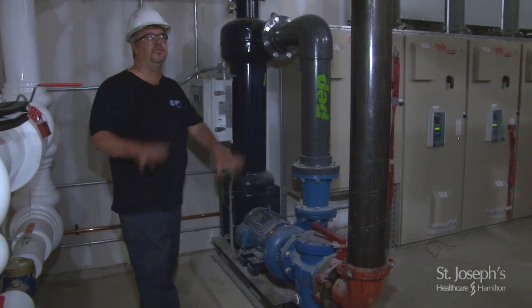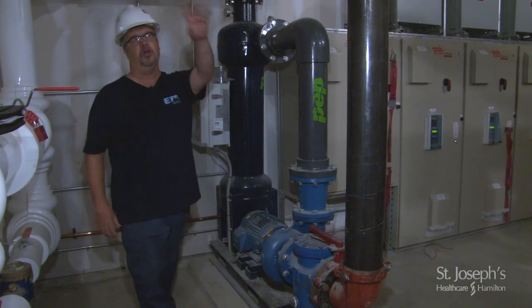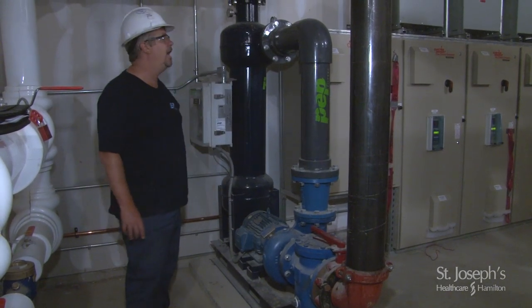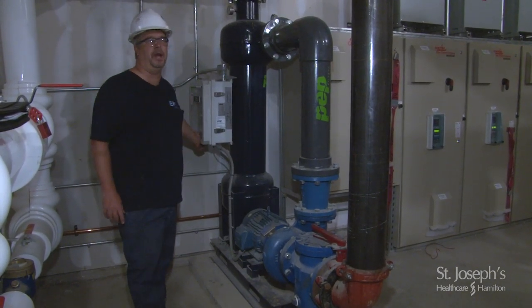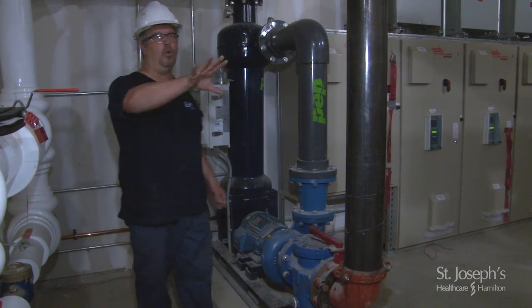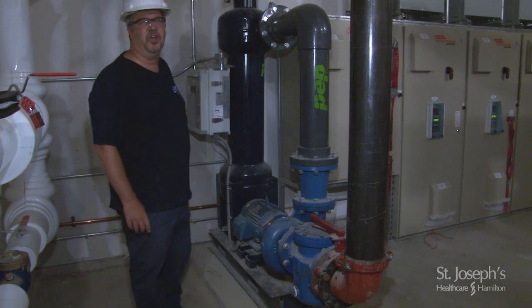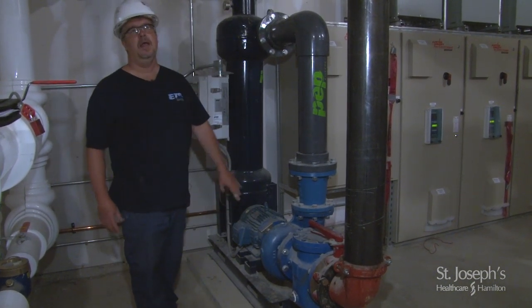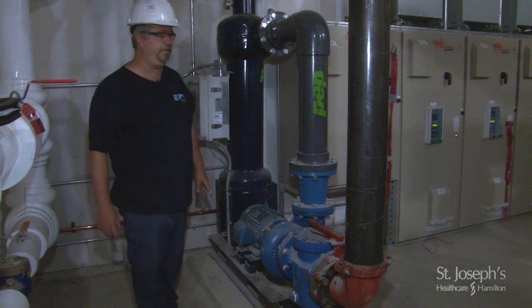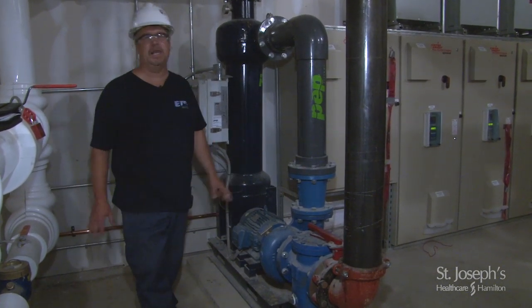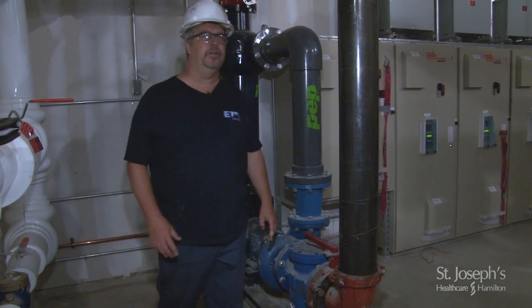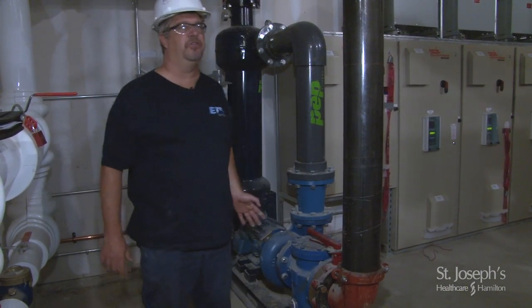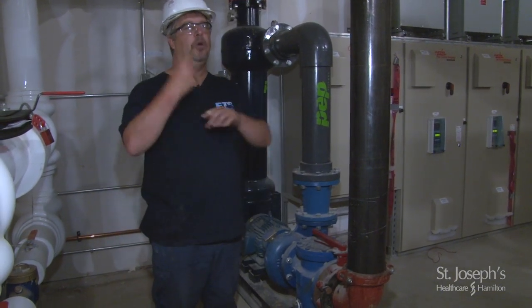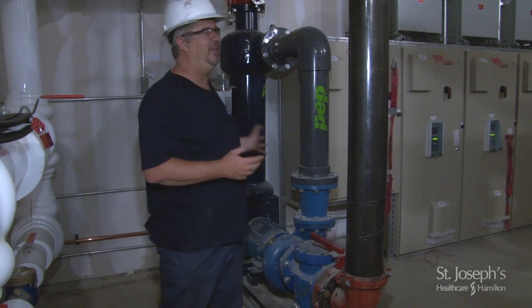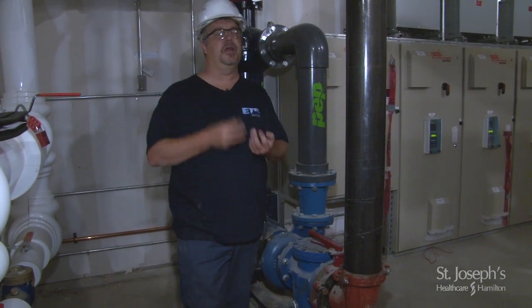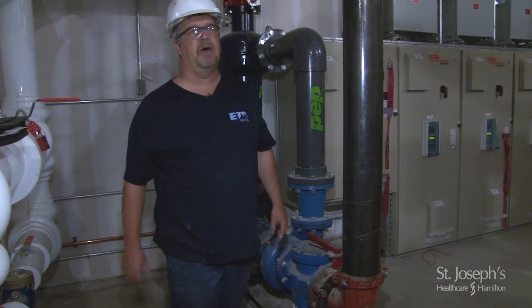If you are shutting the systems down to do maintenance on the pumps or the filter or the cooling towers, you should not leave this in the running position. In other words, if you're not flowing water from the pumps, then don't run your filters because the pumps don't like to run dry. They want to have water going through them all the time. Other than that, these would just be left in the on position, and there is very little you can do as far as maintenance is concerned. I will be leaving on site a copy of the operation and maintenance manual, as well as an electronic copy that will be sent to you so that you can have it for permanent records.